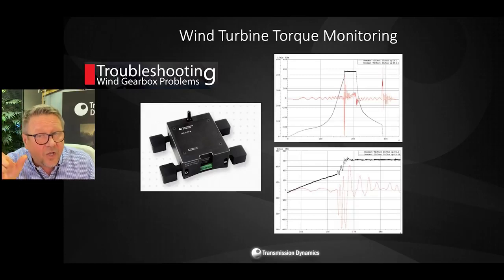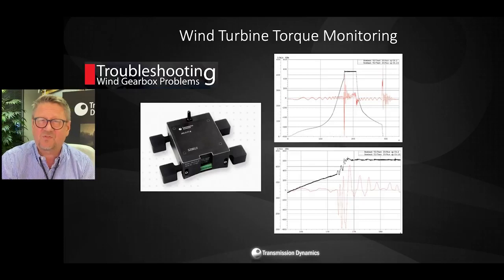gradually accelerating to the synchronous speed with the grid, and then on this occasion we actually connected the wind turbine just slightly prematurely. What that really means is that instead of the wind turbine generating power and sending that to the grid, it is the grid realizing I'm running at 50 Hertz, I'm not going to change my frequency, my inertia is actually too high, my 50 Hertz will never be changed. When you're connecting now and you're running too slowly, then it is the grid which will effectively inject the power into the wind turbine to effectively rapidly accelerate the wind turbine output shaft and the generator to the synchronous speed. During that very process, you can see in the bottom graph, significant oscillations may occur, and this torque reversal is very unhealthy in terms of operation of the bearings, not so much gear elements.